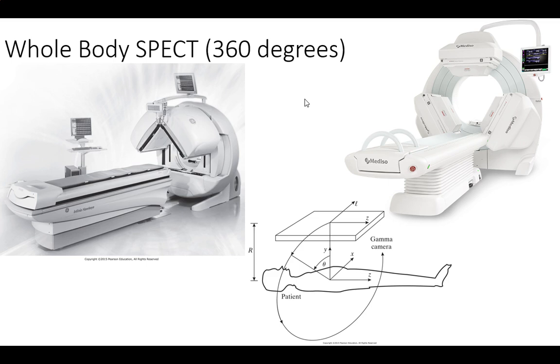That's true. And these beds are usually made out of carbon fiber. The reason is carbon has a very low Z, but carbon fiber is very stiff. So it won't really appear on your image very much, but it's very, very stiff, will hold people well, and it's lightweight. So usually those slide-in beds are something like carbon fiber. That's essentially going to be invisible. The radiation will actually damage them, so every 6 months to a year they become a little more brittle, and you just throw them out long before it's ever a problem and replace them. But you'll be able to see all the way around.